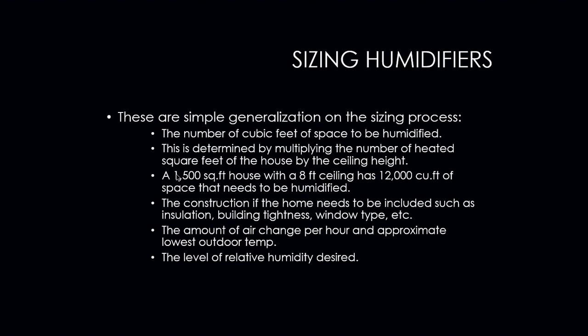Okay, the construction of the home is also important. We need to know what it's made of, what type of insulation is in the walls, how tight the building is, the types of windows. Are they single pane? Are they double pane? And in fact, it's really good to know the building orientation. Which way is the building facing? North, south, east, west? The reason is that we need to know what part of the home is going to be receiving the brunt of the wind and the coldest part during the winter months. The amount of air changes per hour and the approximate lowest outdoor air temperature that the home is going to be susceptible to.